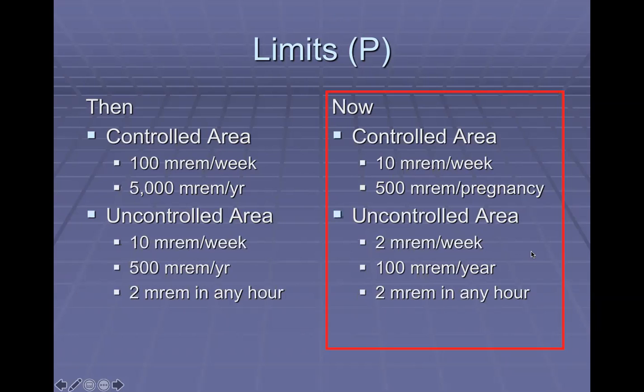So really, I want you to try to think about this. This is just one more thing you have to remember for a quiz, for a test. But if you remember your dose limits and the appropriate dose limits, then you can always calculate these values based off of the annual limits. You can calculate your weekly design goal based off the annual limits. So if you just remember that we're designing for ALARA principles and for pregnant staff, so that's that 500 millirem limit, and the 100 millirem limit for a member of the public.